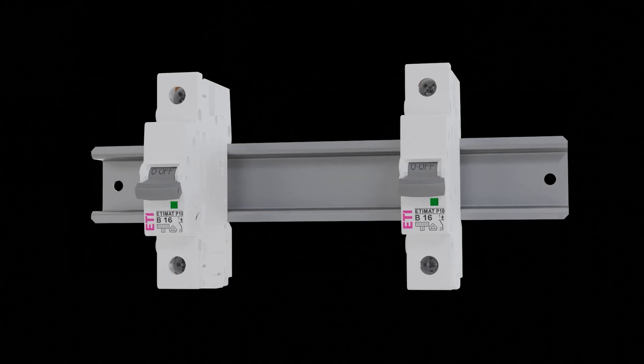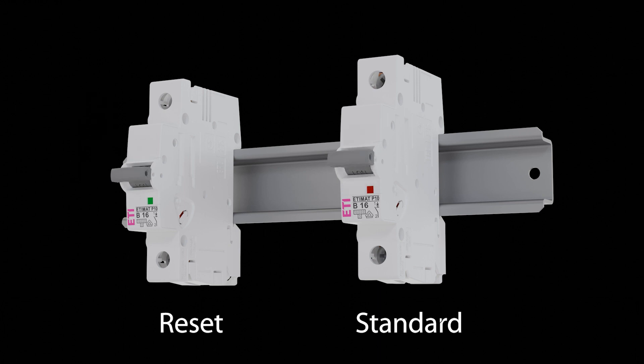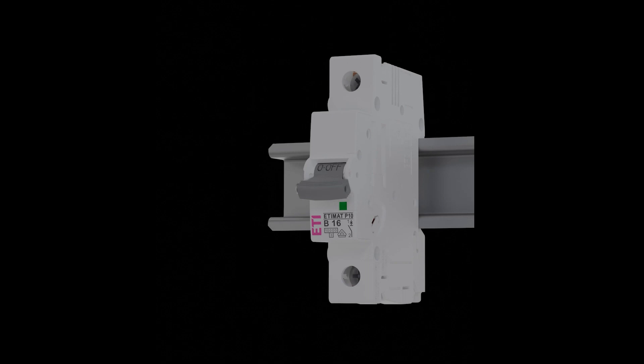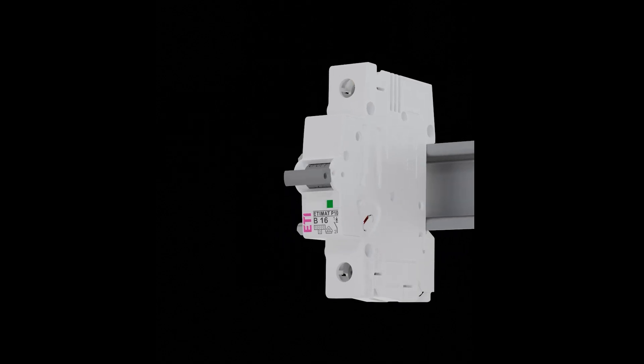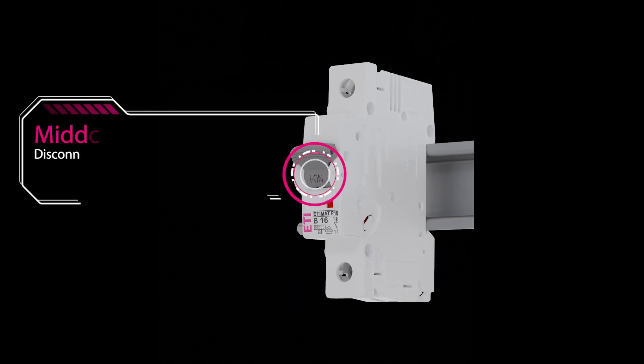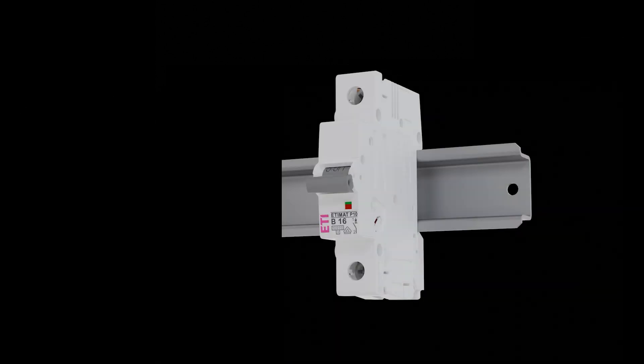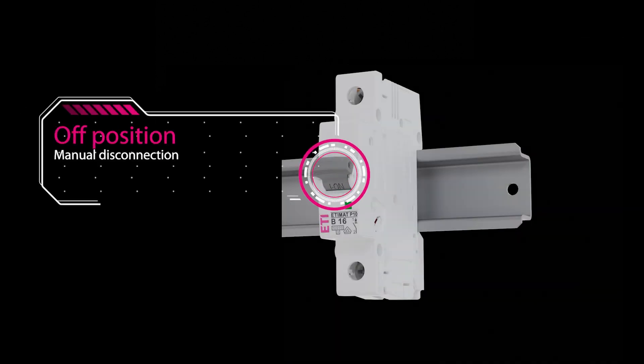ETIMAT P is available in a standard or special reset version. In the special reset version, the position of the on button indicates the reason for the disconnection, preventing user errors and always clearly indicating whether the system was manually switched off or due to a fault in the electrical circuit. In the event of overload or short circuit, the button is moved to the middle position. If the button is in the off position, we know it was a manual disconnection.